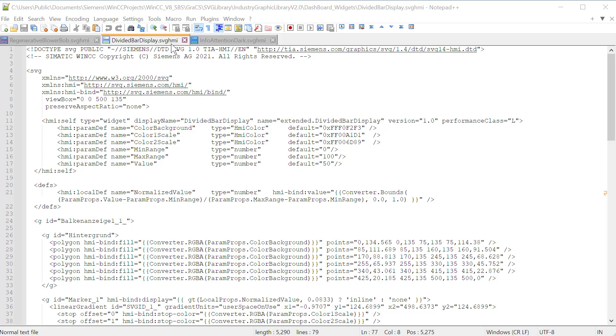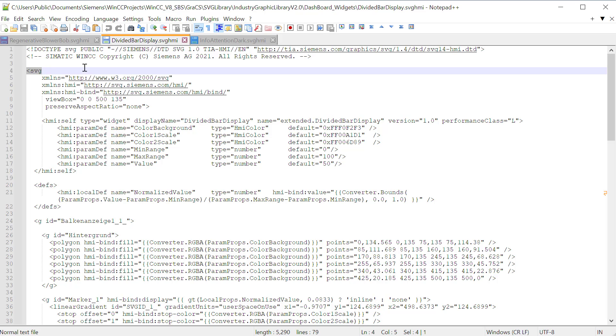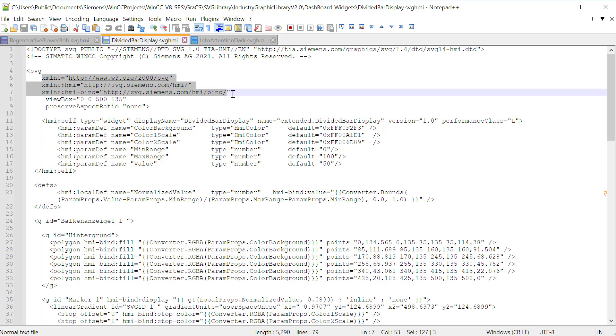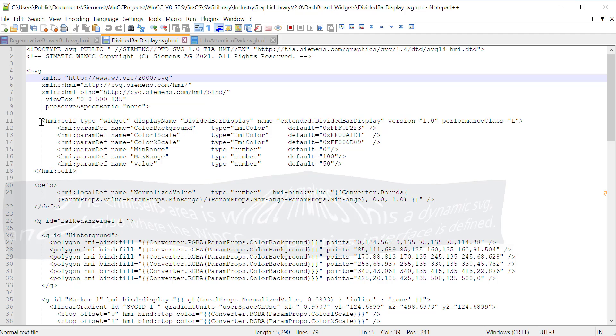Note that it has the file extension SVG HMI. This is a special file type that is defined by Siemens based on the SVG standard. This top part is called the document type declaration. So they're declaring it as a Siemens document type. And then we start our regular SVG definition. And this is your namespaces here. So it uses the standard SVG namespace. And then Siemens adds their own namespaces for the interface into their graphics designer. So we have a HMI namespace as well as an HMI bind, which is how we are able to interact with tags and scripts and things like that on the property interface.